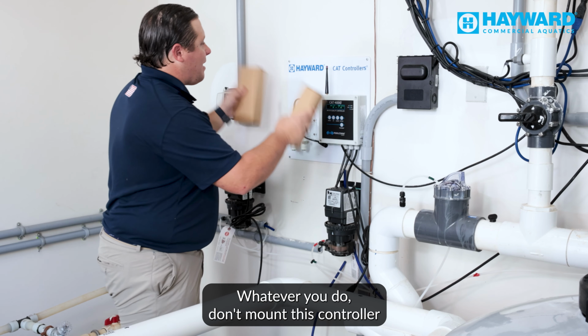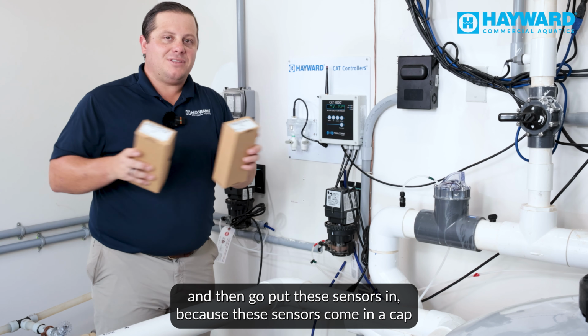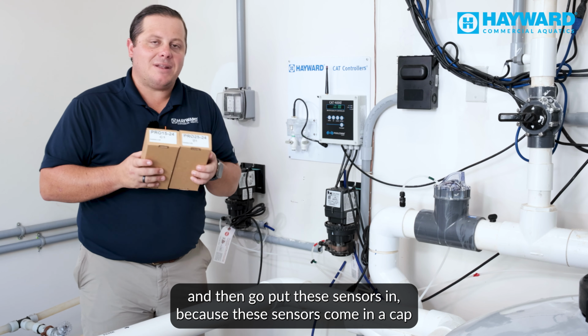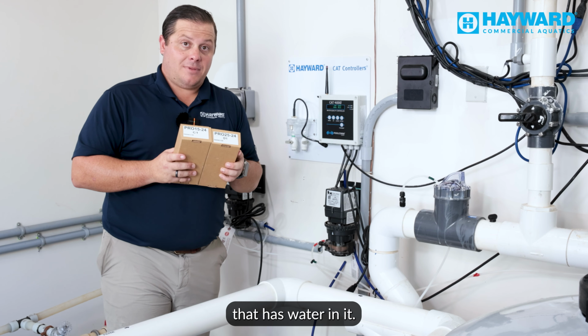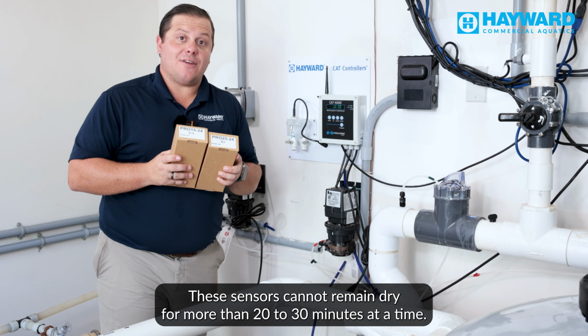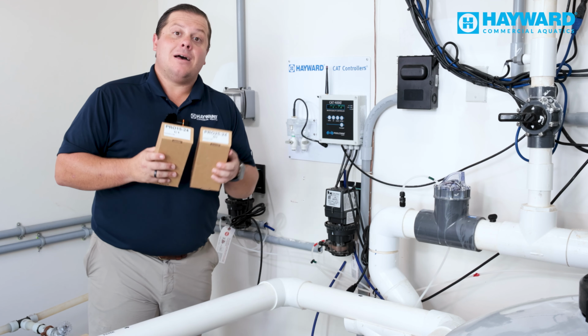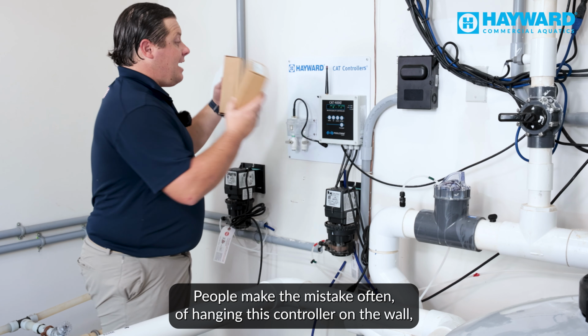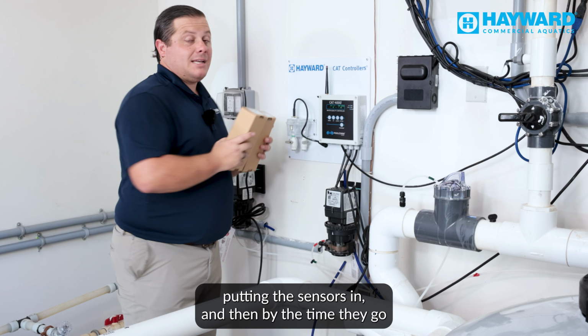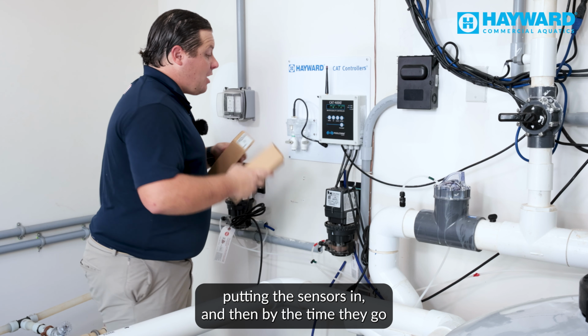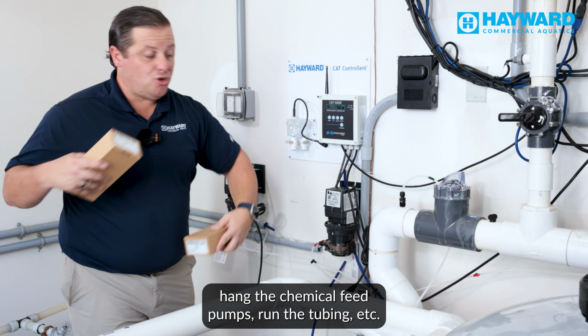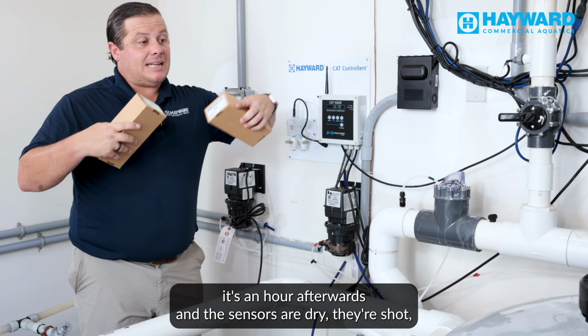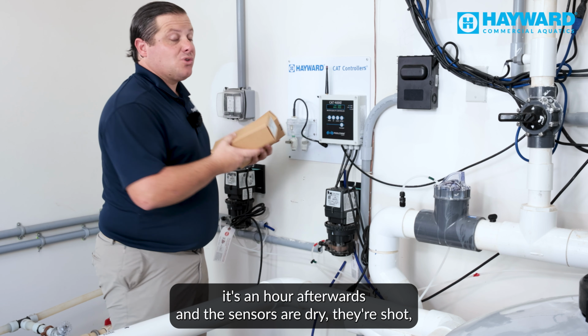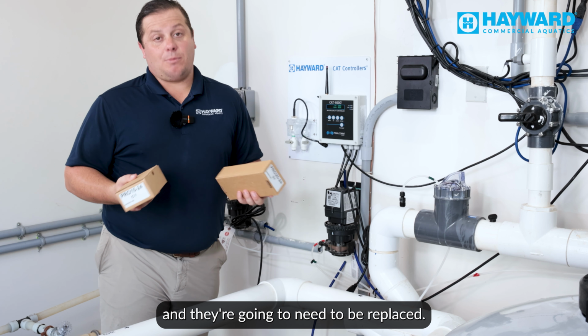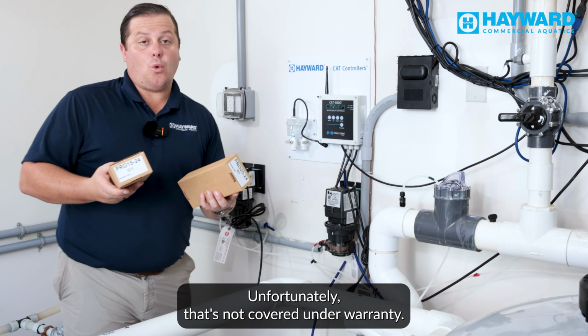Whatever you do, don't mount this controller and then go put these sensors in, because these sensors come in a cap that has water in it. These sensors cannot remain dry for more than 20 to 30 minutes at a time. People often make the mistake of hanging this controller on the wall and putting the sensors in, and by the time they hang the chemical feed pumps, run the tubing, etc., it's an hour afterwards and the sensors are dry. They're shot and need to be replaced. Unfortunately, that's not covered under warranty.